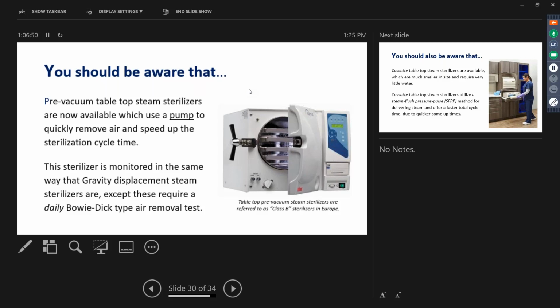So let me see if I understand this correctly, Jeff. I can buy a $3,500 gravity sterilizer and not run that $3,000 a year test, or I can buy a $6,500 pre-vac sterilizer and on top of that have $3,000 worth of special testing done. I wonder what they're going to choose to do.